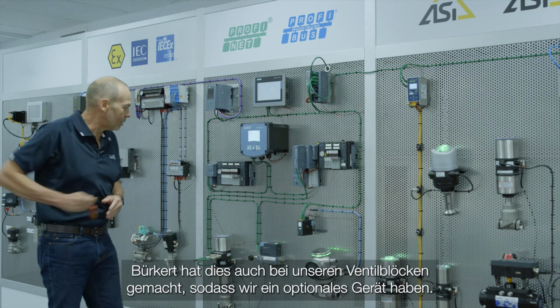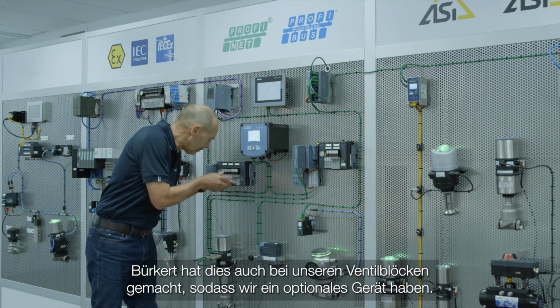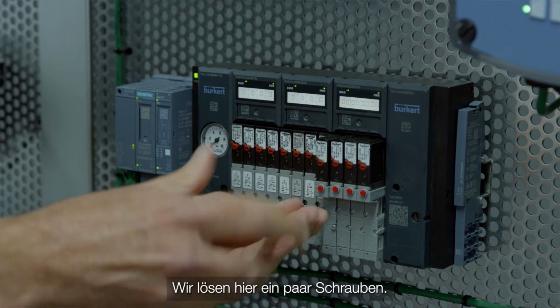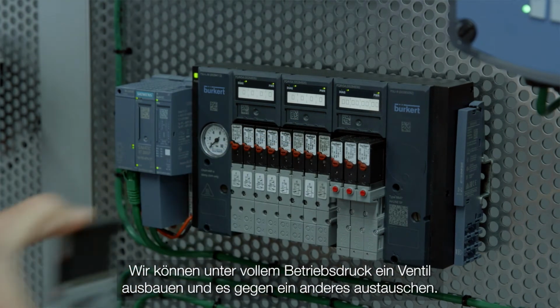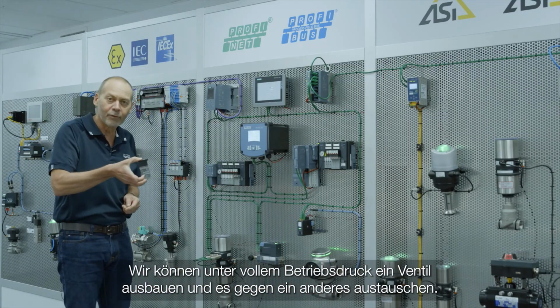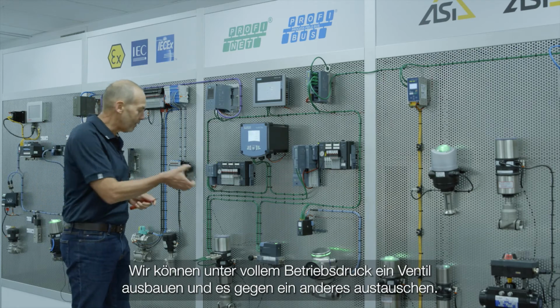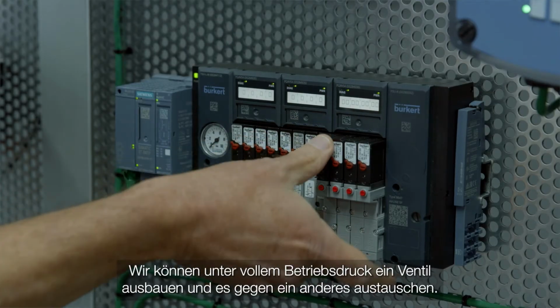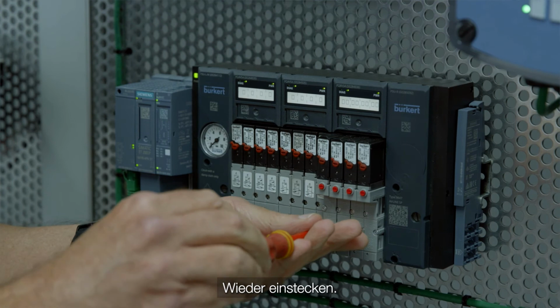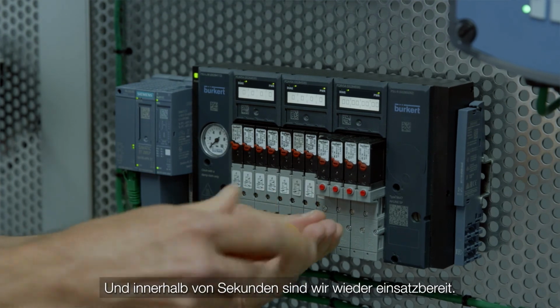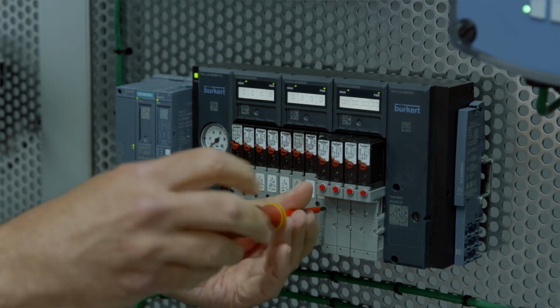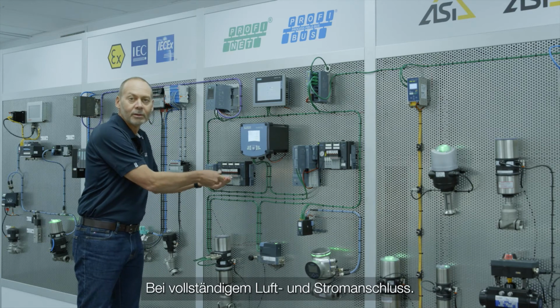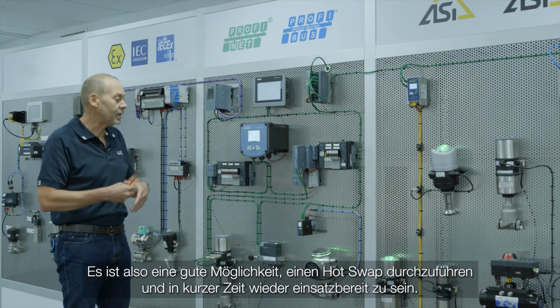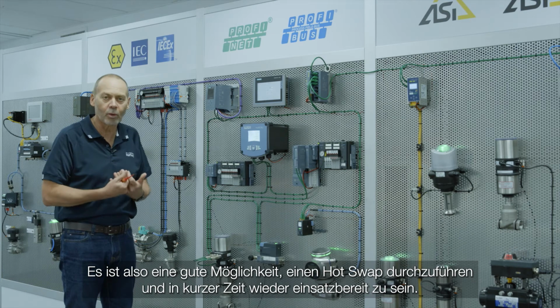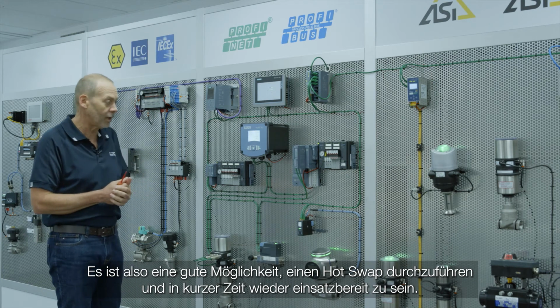We have an optional device where, undoing a couple of screws, we can, under full operating pressure, remove a valve, change it for another valve, and replace it, and within seconds we can be back up and running under full power and under full air. So it's a good availability to have, a hot swap, and get up and running in a short period of time.